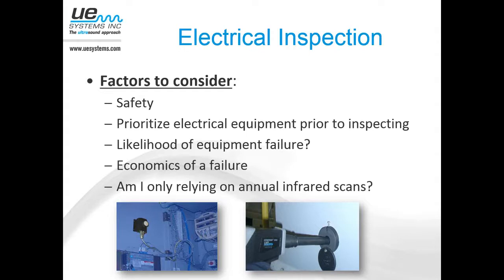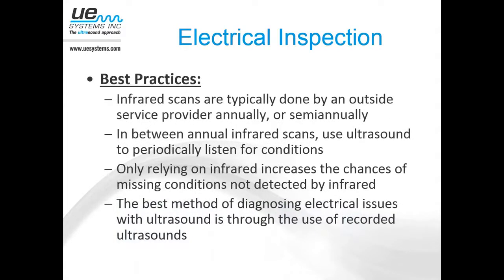So ultrasound really is a big partner to the infrared industry in that way. Not to mention there are so many problems we can find with ultrasound on its own. So again, some best practices for electrical infrared scans: usually done by an outside service provider. I know some companies do it internally, which is great, but a lot of plants use an outside contractor annually or semi-annually. In between those scans, you want to use some ultrasound to periodically listen for problems. You can almost use it to direct the infrared guys where to go do further inspection.